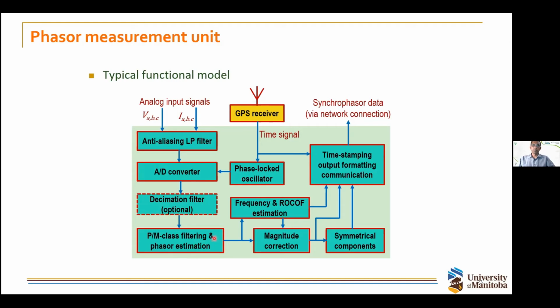So here is what is happening with the phasor estimation. And also we need to do some sort of filtering, depending on the accuracy class requirements. After that, you can use the phase angle measurements to compute the frequency and the rate of change of frequency. When you calculate the frequency, if the frequency is not exactly at the nominal frequency, typically you need to do some correction to the estimated magnitude. And that magnitude correction is applied here.